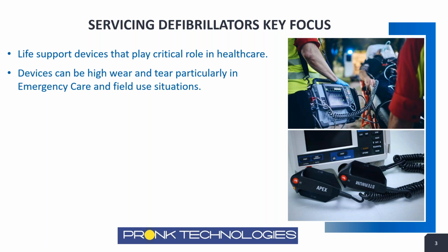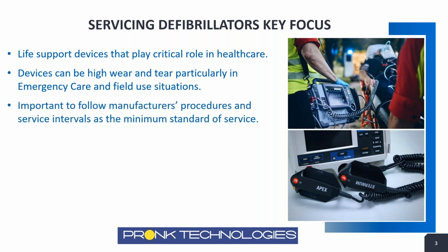They're really high wear and tear devices, as you know, particularly if devices are used in the field. And so it's important that not only do we do the common things we do in testing these devices, but really pay attention to the wear and tear. And we'll give you some examples of some situations that have happened regarding that. And it's important to make sure we're following the procedures from the manufacturers.